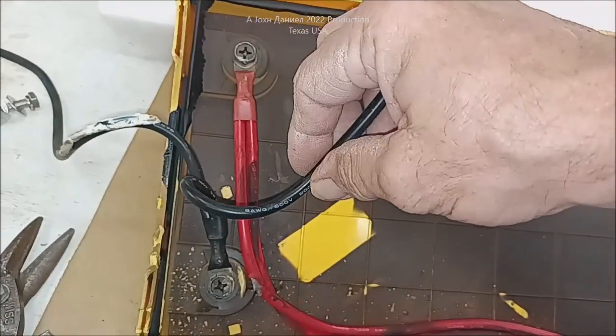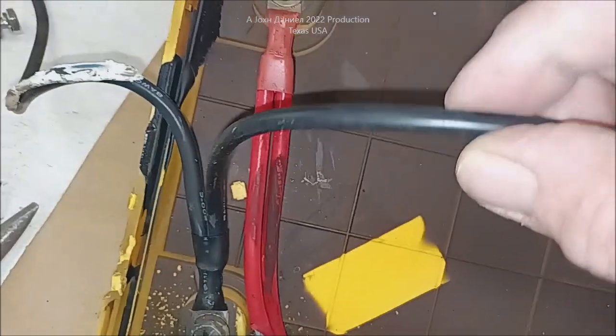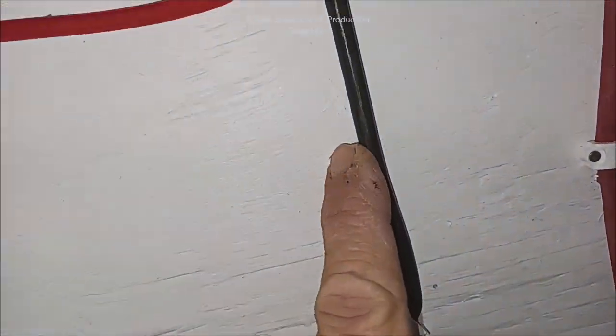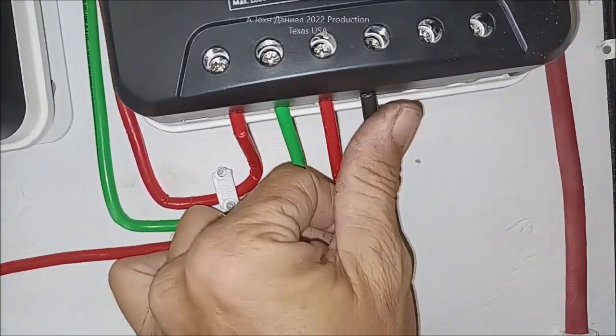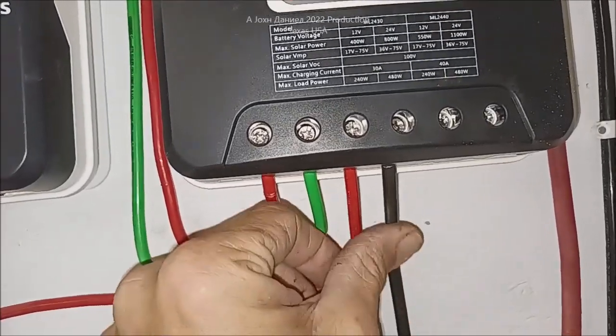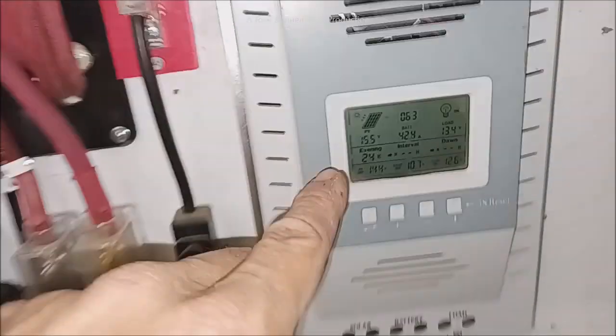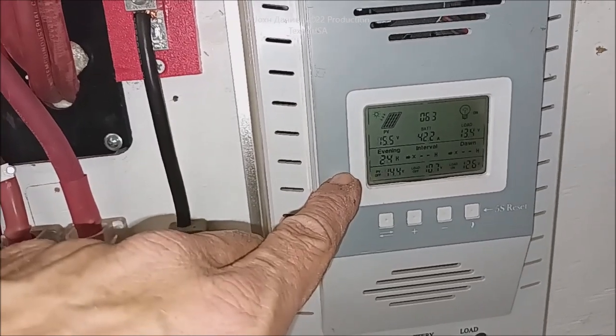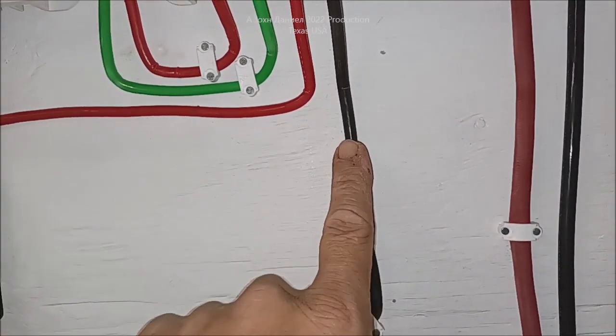What I'm doing with this video is giving you a forewarning: these things are no longer being built with anything substantial in them. This is just 8-gauge wire — see that. I don't know how in the hell you're going to be putting 100 amps through with a pair of 8-gauge wires. This 8-gauge here is running 26 amps right now and it's not hot, but it'll warm up. Over at my panels it's running about 34 to 38 amps, getting shaded now. At 32 to 35 amps on 8-gauge wire, it'll get warm — and over here the other wire is 4-gauge. That is inadequate.